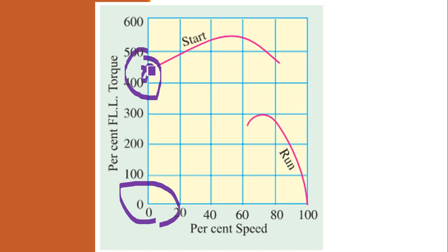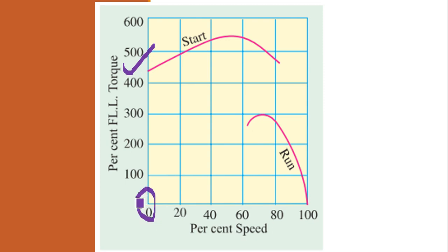So at start, how you are understanding it is at start, this is at 0 speed. It is not rotating, but the torque is still available. So this is known as the starting torque point. It is giving almost 430%, that is more than 4 times the full load torque.